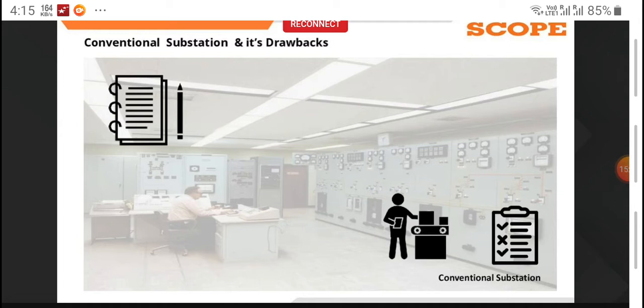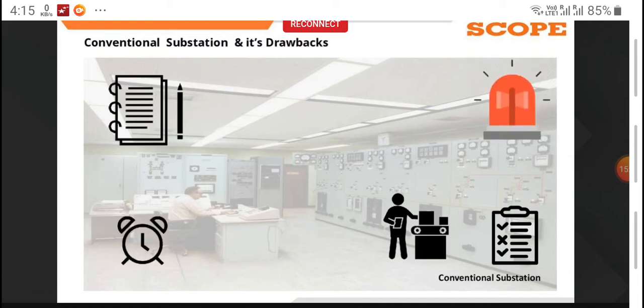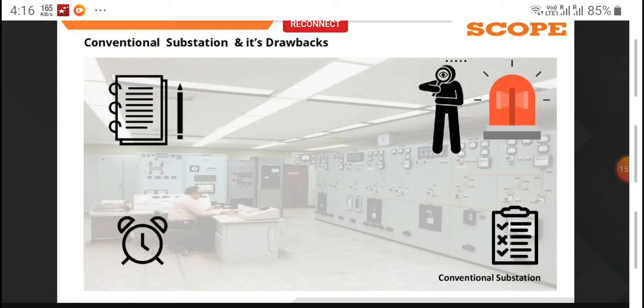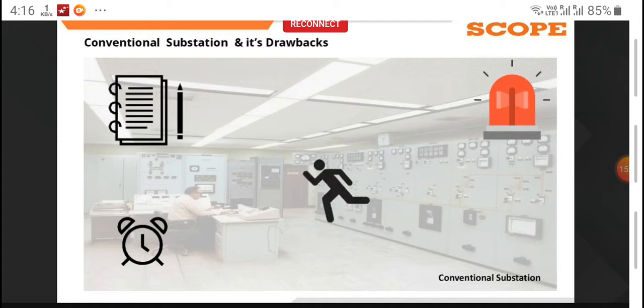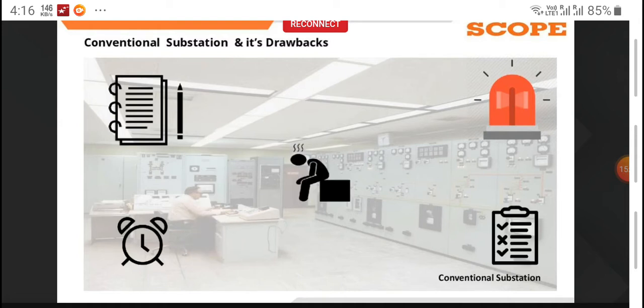He writes in the ledger, and in between, while doing this, if any alarm comes or any event happens, the breaker trips or anything happens, he has no clue what exactly happened. So he has to drop everything and run to the control panel and see what exactly happened there. Then he has to run to the alarm system and reset the alarm. Then he has to run and put all these events in the log.